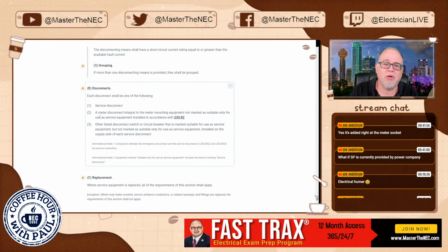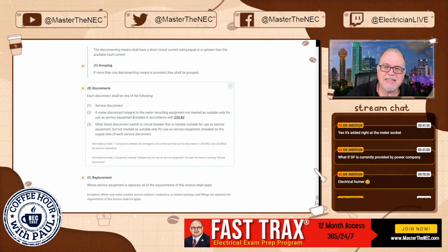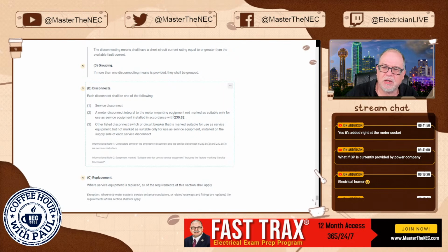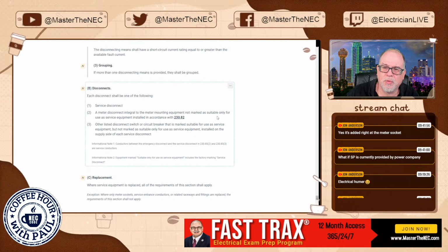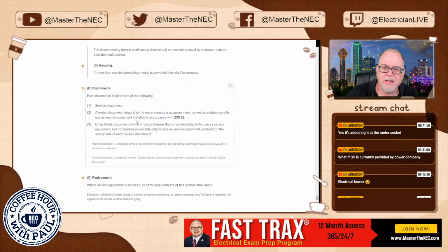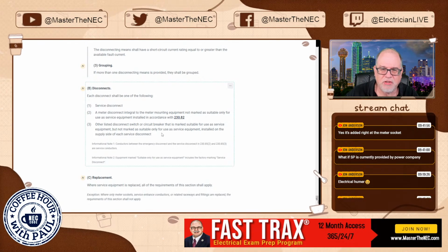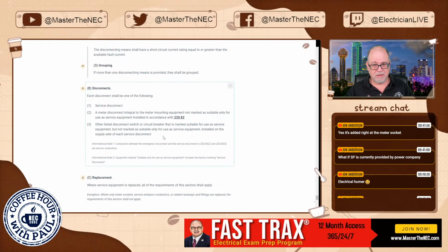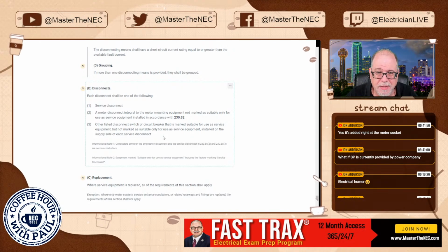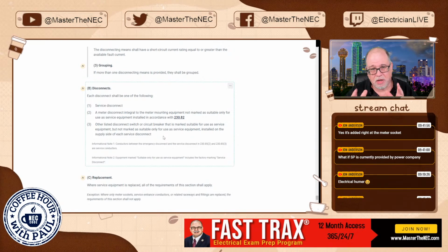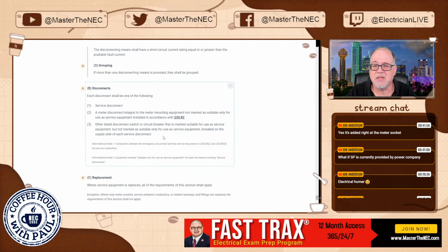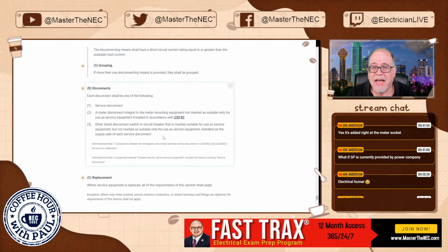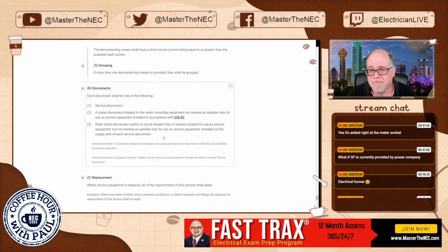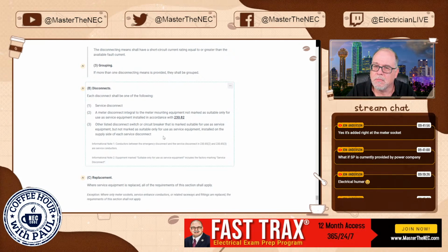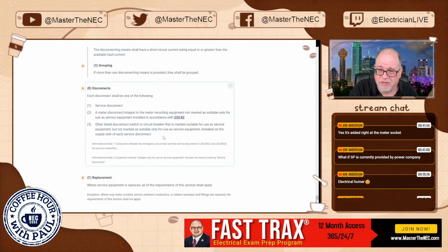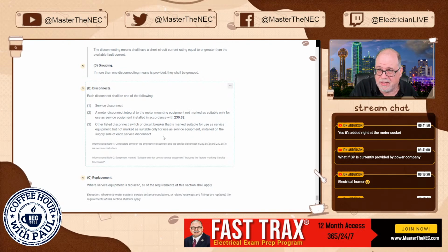Number 2, it says a meter disconnect integral to the meter mounting equipment not marked as suitable only for use as service equipment installed in accordance with 230.82. So you can have a meter disconnect that's integral to the meter mounting equipment in the enclosure. Well, if that's the case, that's okay to be used as an emergency disconnect. Now, remember something though. That is not a service disconnect. That's just a meter disconnect.